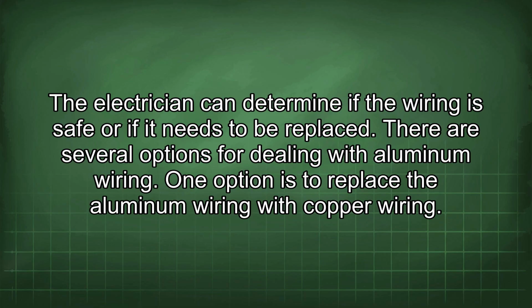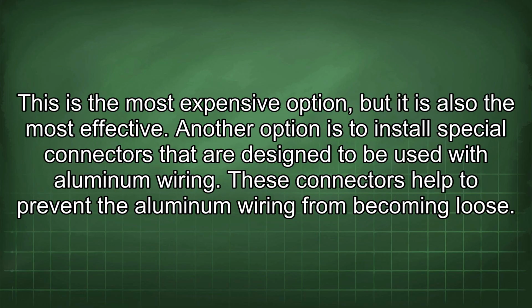There are several options for dealing with aluminum wiring. One option is to replace the aluminum wiring with copper wiring. This is the most expensive option, but it is also the most effective. Another option is to install special connectors that are designed to be used with aluminum wiring. These connectors help to prevent the aluminum wiring from becoming loose.